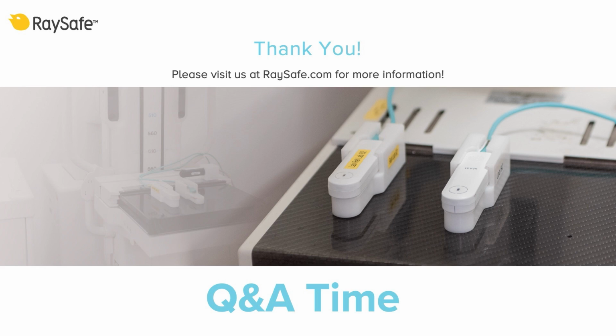The 452 has a fast startup, meaning you can use it right away, while a 451 or more or less all ion chambers need to be idle for a minute or so before use. It also has a faster energy or dose rate response. So the 452 can detect a step in the dose rate faster than the 451, for example.